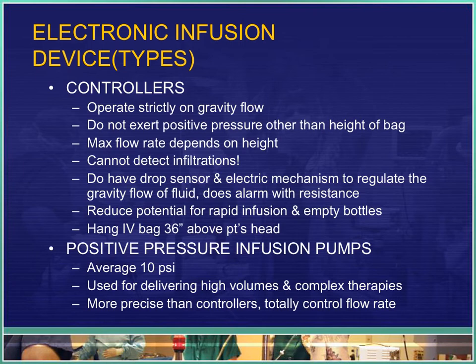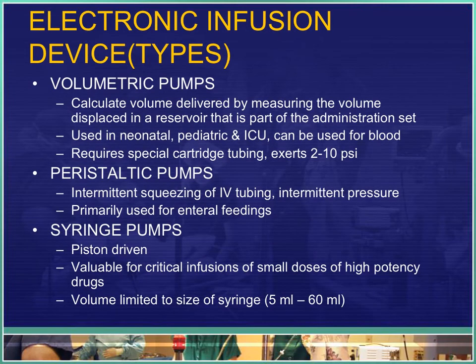Positive pressure infusion pumps average 10 psi. They are used for delivering high volumes of complex therapies and are more precise than controllers and totally control the flow rate. Volumetric pumps calculate the volume delivered by measuring the volume displaced in a reservoir that is part of the administration set. These are used in the neonatal, pediatric, and ICU settings and can also be used for blood administration. They require special cartridge tubings and exert 2 to 10 psi.